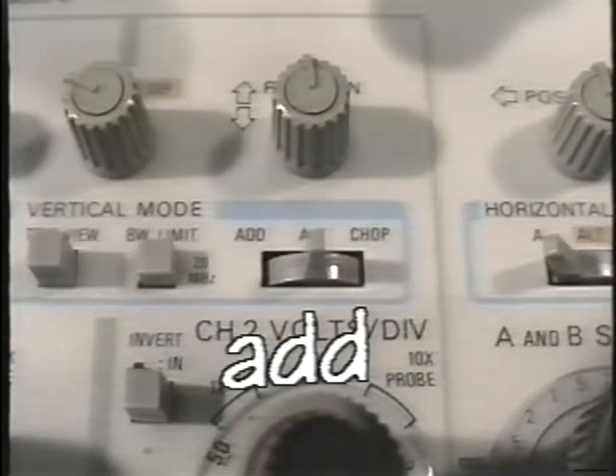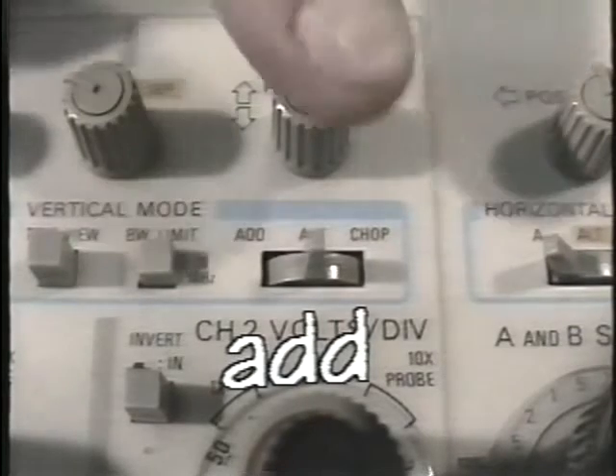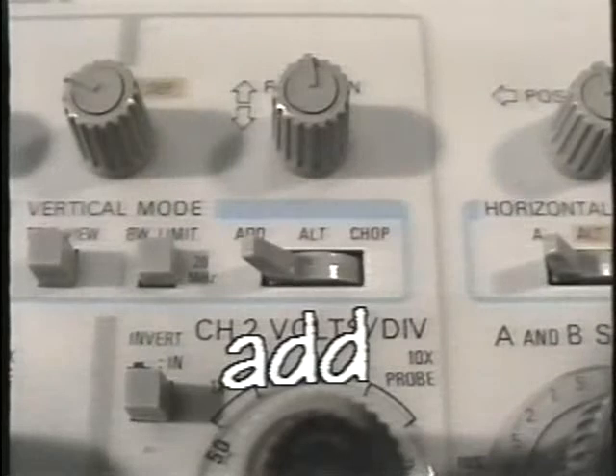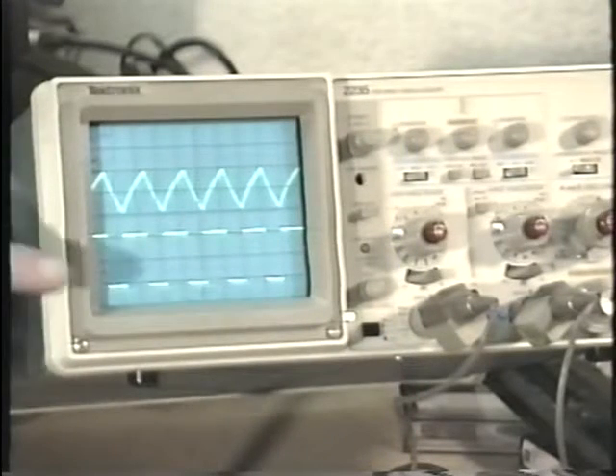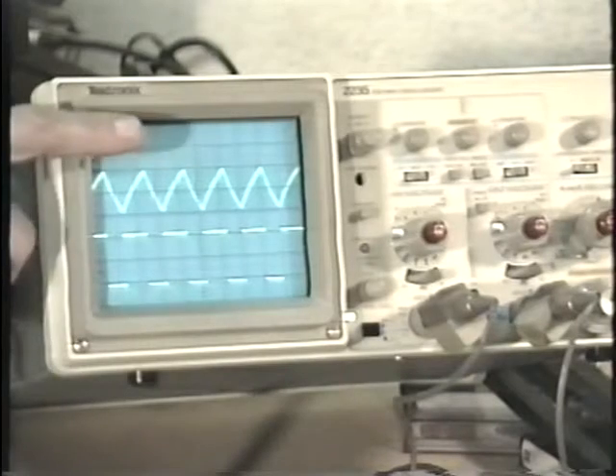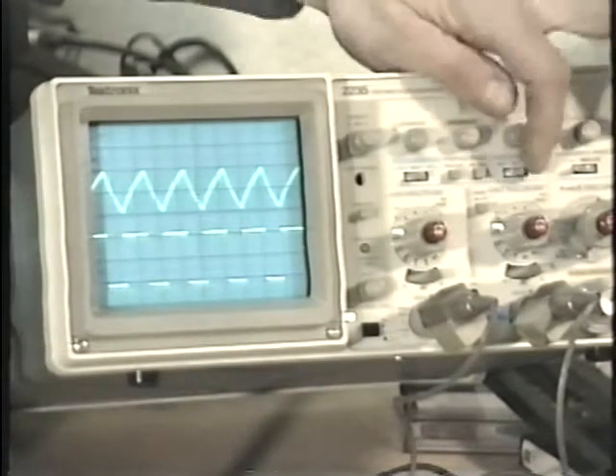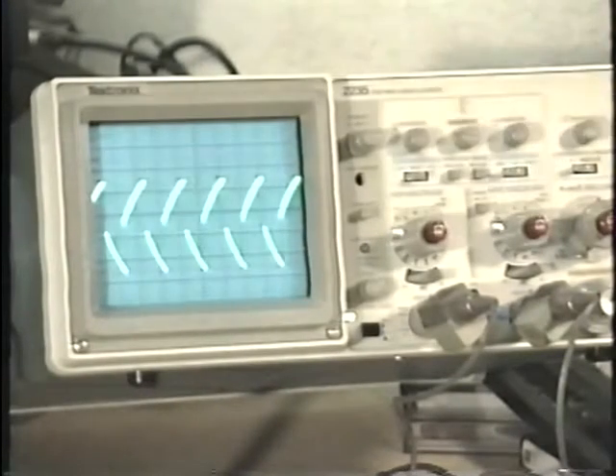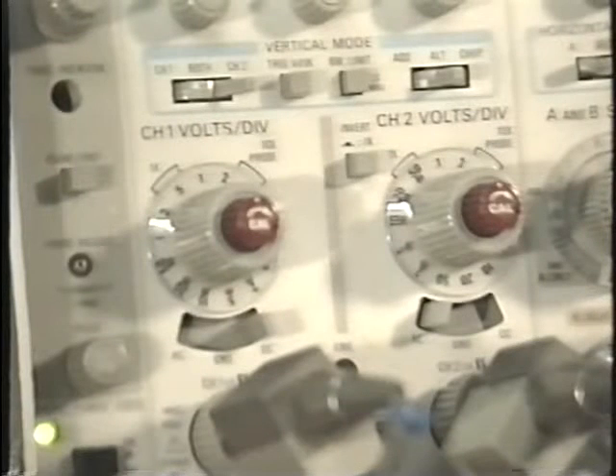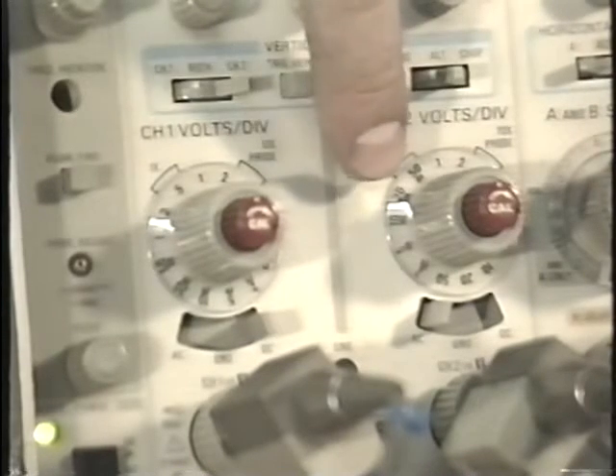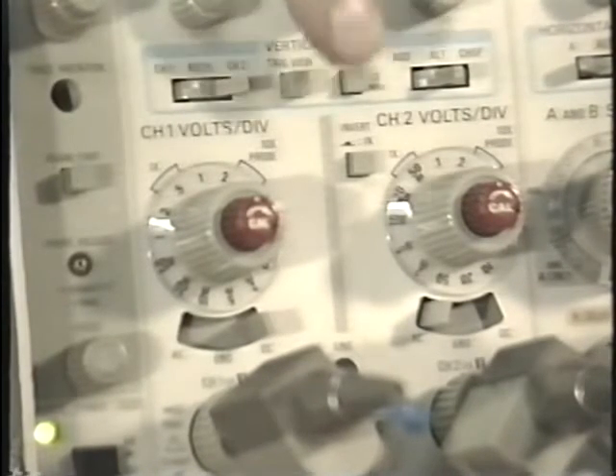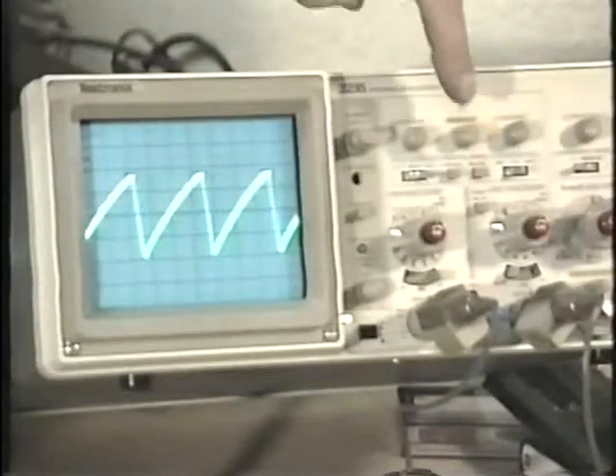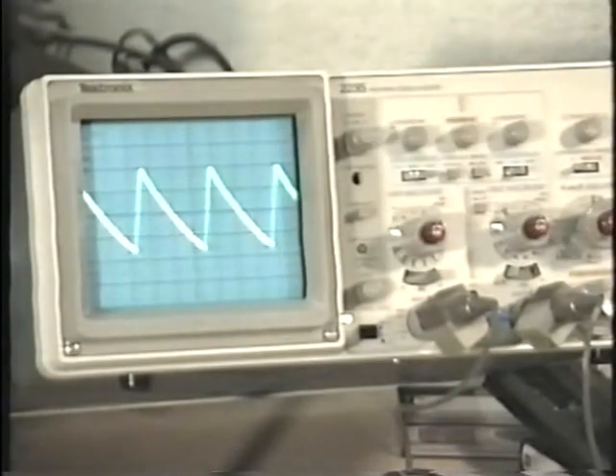There's another vertical mode setting on this oscilloscope. It's called add. This setting takes the input at channel 1 and adds it to the input at channel 2. The result is shown on the display. At first glance, the 2 vertical channels look identical, but channel 2 has one extra button. It's called the invert function. When the invert button is pressed, the channel 2 input is flipped upside down.